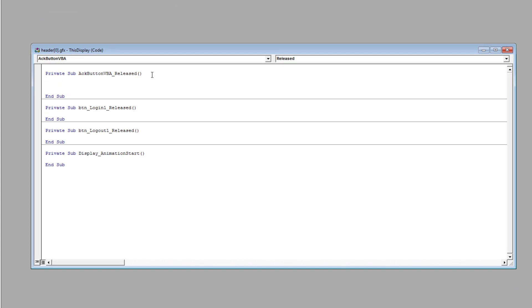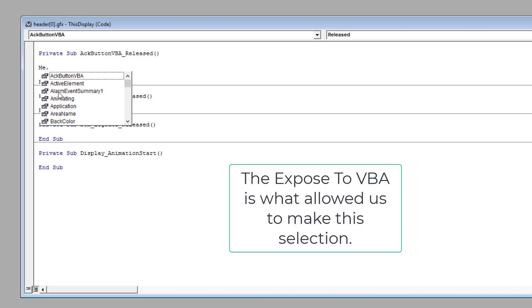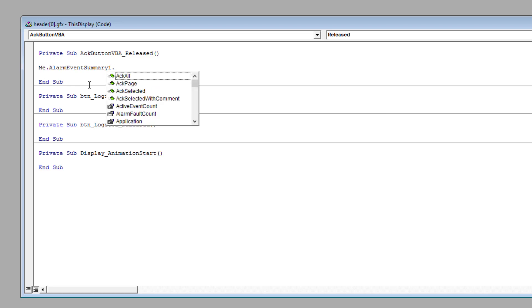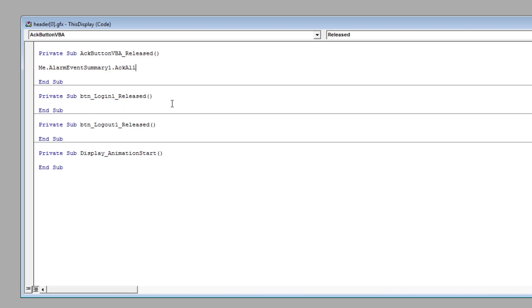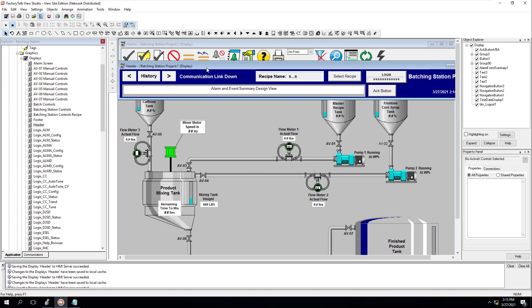Let me show you how to type this out. In the application you're going to type 'me dot' and then choose the alarm summary. If you had not checked 'exposed to VBA code', it would not have populated. Now we have that, and we can come over here and select acknowledge all. That's just that simple on how to do that.